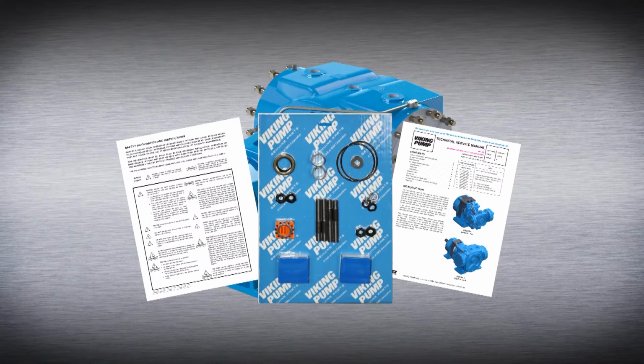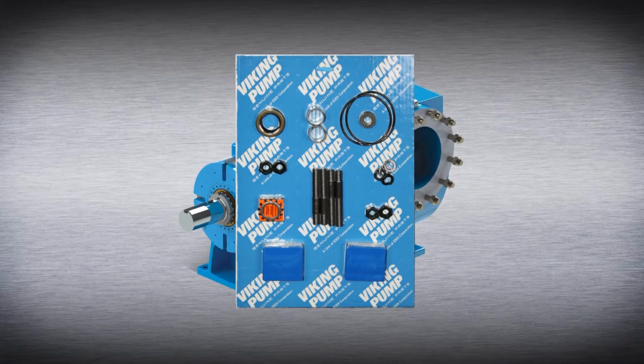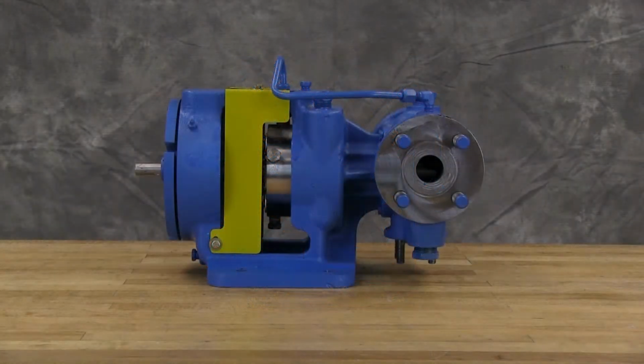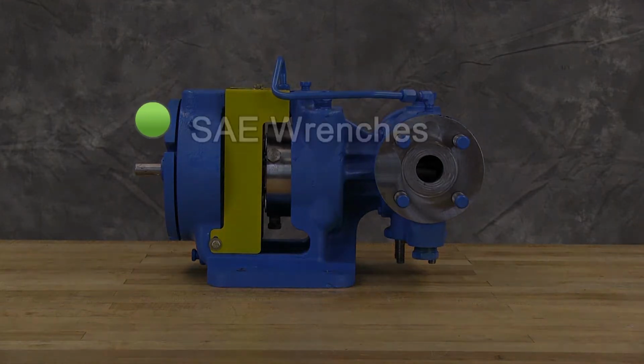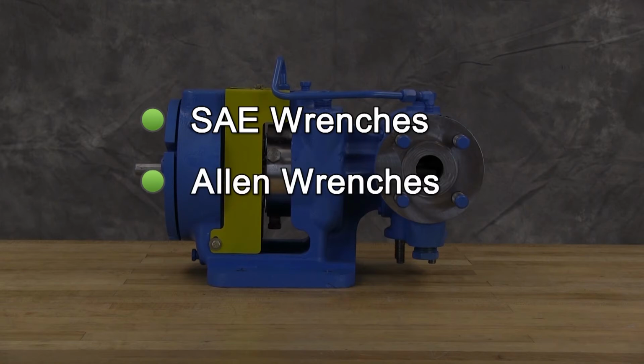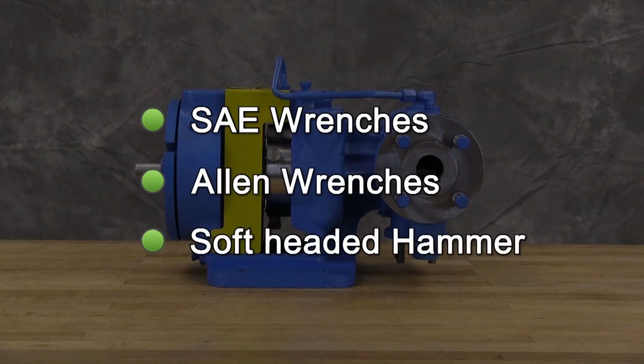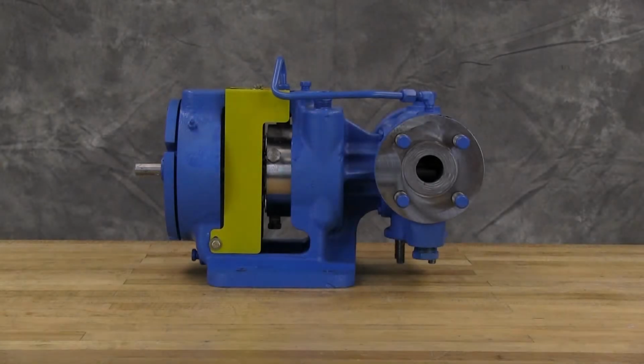For this series of pumps, bearing kits are available. Contact your local authorized Viking pump distributor with the model and serial number of the pump to obtain this kit part number. The bearing kit includes bearings, collars, lip seals, O-rings, and associated hardware. You may require the following tools for disassembly and repair: SAE wrenches, Allen wrenches, and a soft-headed hammer. A complete listing of tools and part numbers can be found in the service manual.